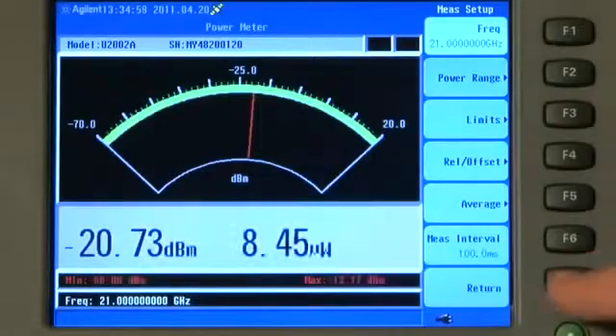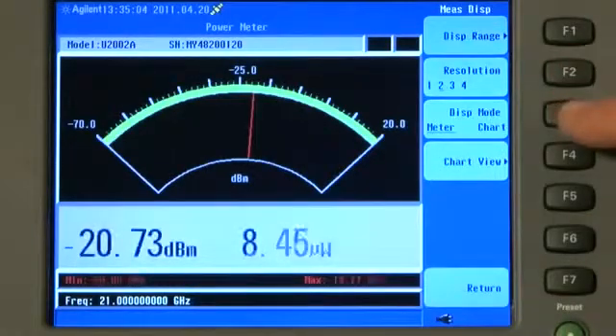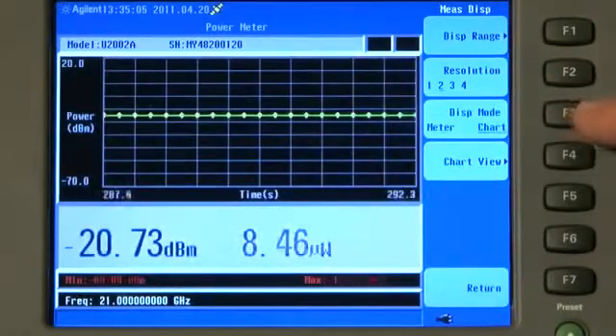But what's even better, if I press Return and press Meas Display, you'll see that we can change the Display Mode to a Chart Recorder. On the Chart Recorder Display, we have Time on the X-axis and Power in dBm on the Y-axis.